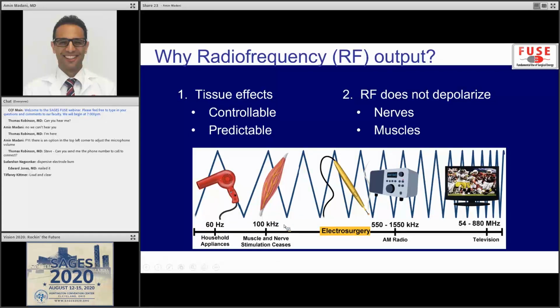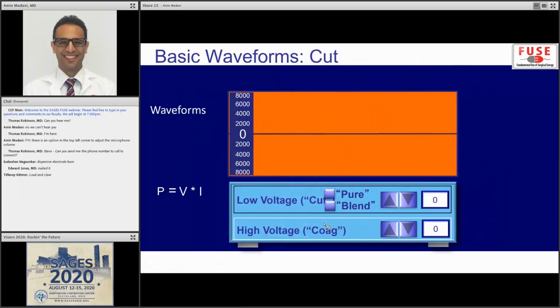Radio frequency is used for a variety of things. When you have two antennas communicating together, that's what they use. Antennas can communicate through air, through an insulator. That's important because the radio frequency electrosurgery we use in the operating room can also communicate to other conductors through air. It's an important principle to remember.